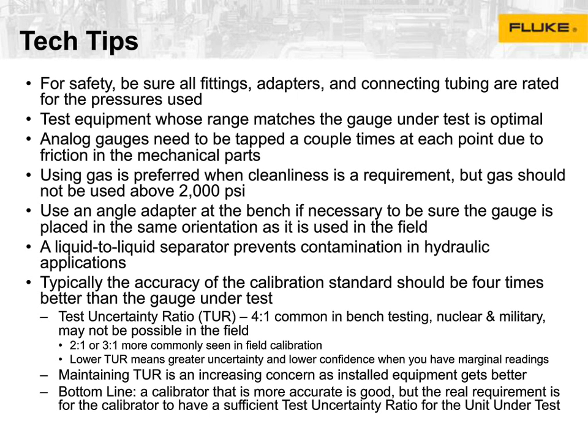We see that people use nitrogen a lot for gauge verification, especially if they're on a bench, because they're right there and it's really easy to recharge your bottle when you get low. It's not a good idea to use it above 2,000 pounds. Really high pressure gas is not a safe thing to be around. We see a lot of this kind of familiarity breeds contempt with high pressure and instrumentation techs, and so we'd really like to emphasize that that's just not good practice. Lower volume ways of getting to high pressure, like hydraulic pumps, are probably the better way to go.